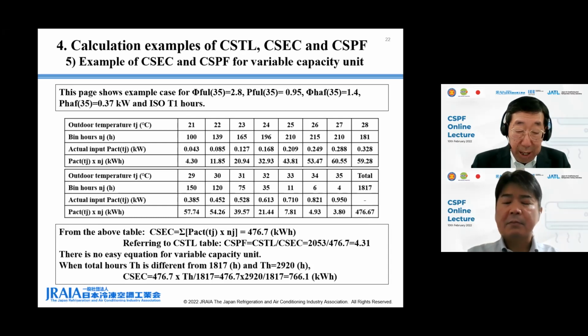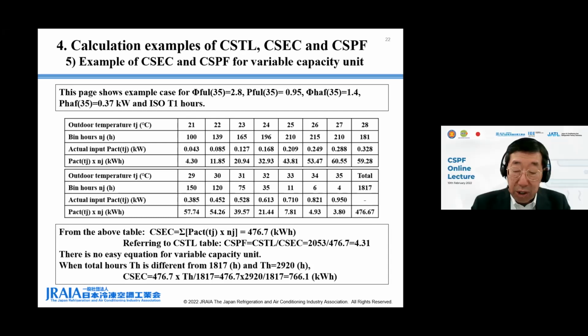Referring to the CSTL table in the previous page, cooling seasonal total load CSTL for this example is 2,053 kilowatt hour. CSPF is CSTL 2,053 kilowatt hour divided by CSEC 476.7 kilowatt hour, equal to 4.31. There is no easy equation for variable capacity unit. When total hours TH is different from 1,817 hours and is 2,920 hours, CSEC is multiplied by 2,920 over 1,817, equal to 766.1 kilowatt hour. Next, please.